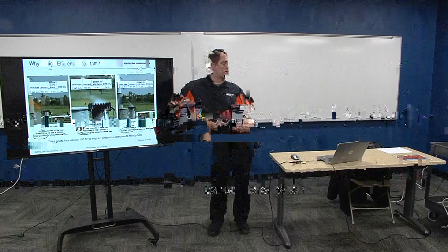All right, that's pretty good. 99.2% is higher than the 98 standard, right? Pretty good. This one, you know, had a little bit extra steam added to it. So if we look at it, we had 20,000 pounds of flare gas going to it. We added too much steam.